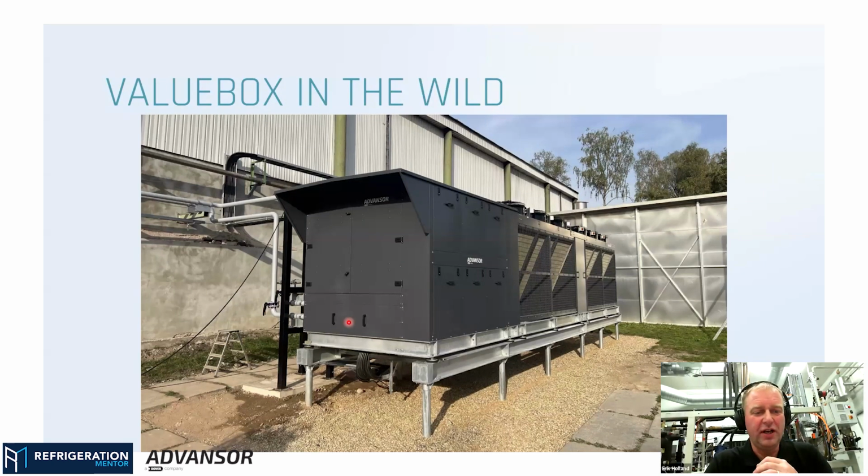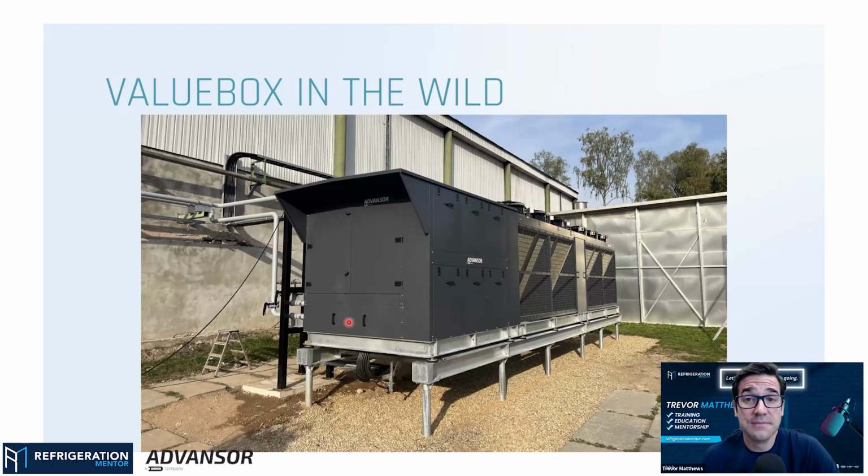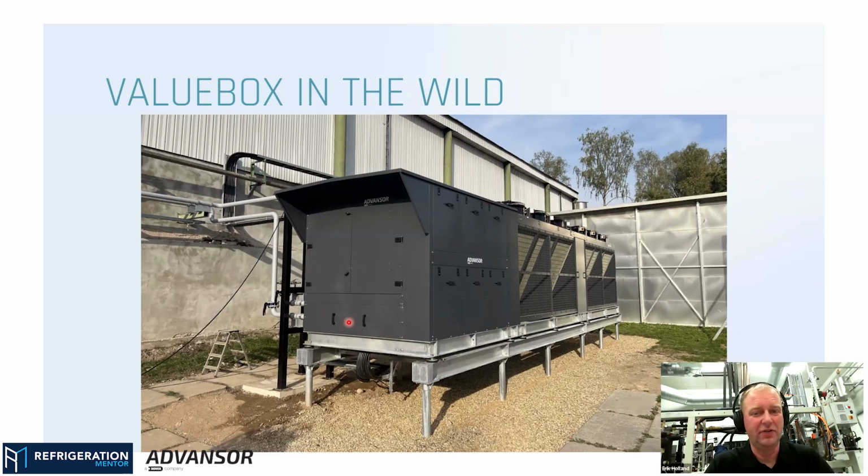That's something the contractor really has to check up on and be sure that all his equipment is also dimensioned correctly and set up correctly, and we verify it. Usually they verify it, because for measuring the overall COP, you have to measure the flow and differential temperatures anyway. So usually they have a metering device on it, so they can tell the flow and the temperature. If you are exporting your heat to a distributed system, there's always some money included as well, so of course they are interested in knowing the correct energy flow in the system. Yeah. So that part of it is fairly easy to convince them that this has to be in order.